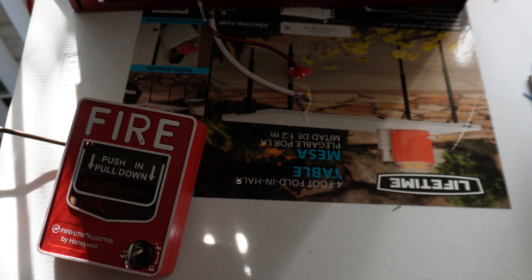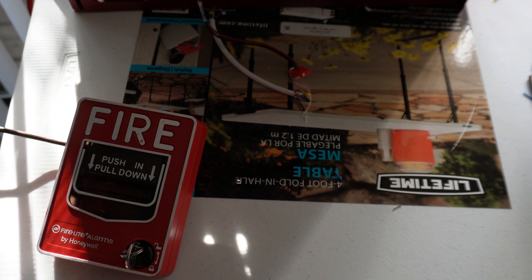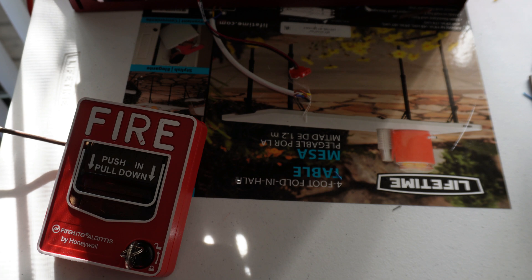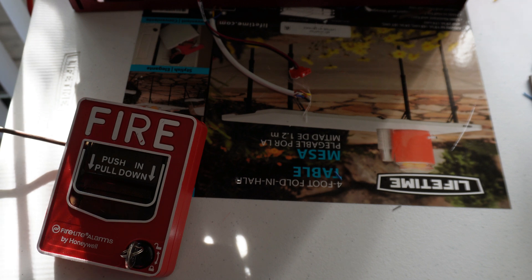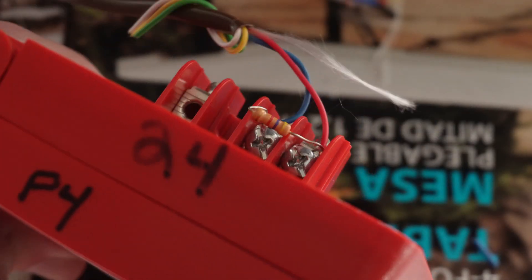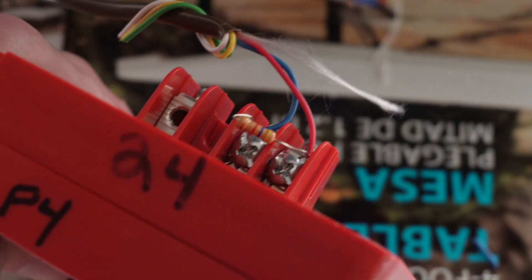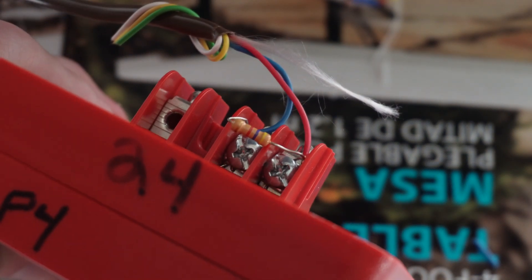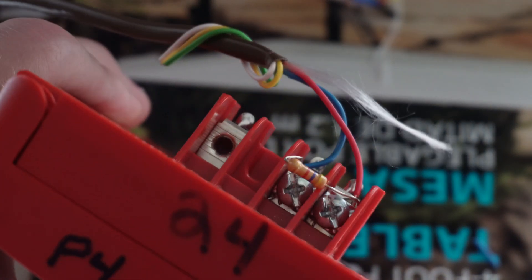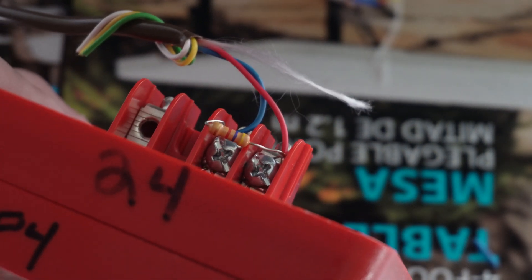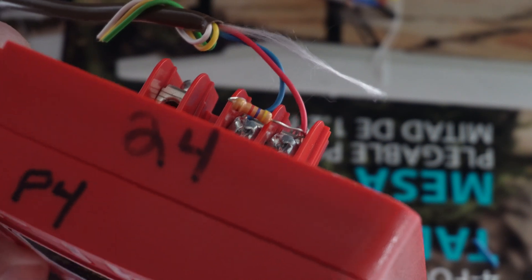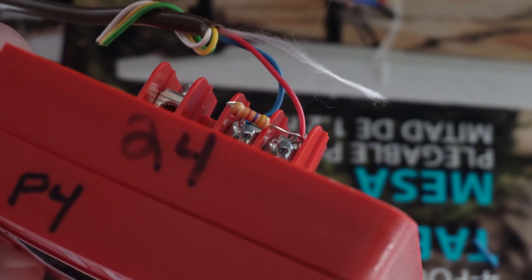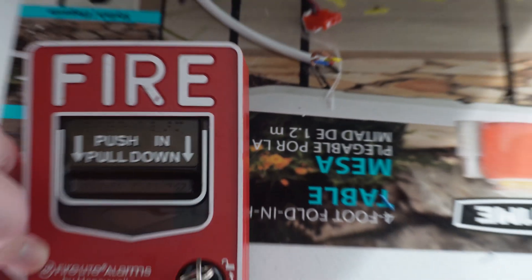As mentioned in the previous video, the way Class B SLCs work is essentially each device that gets wired in is just going to daisy chain off one another. And then the end of line resistor goes at the last device. The smoke is going to daisy chain right off this pull station, right off of the same B plus and negative terminals there. We are also going to move that resistor to the smoke since it will be the last device. That's basically all we are going to have to do in terms of the wiring.